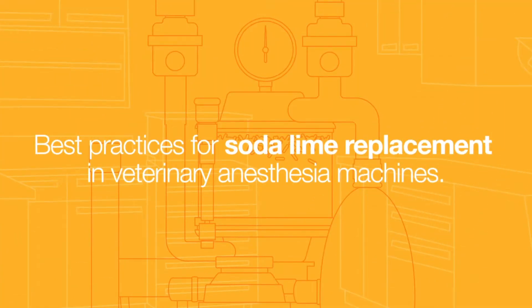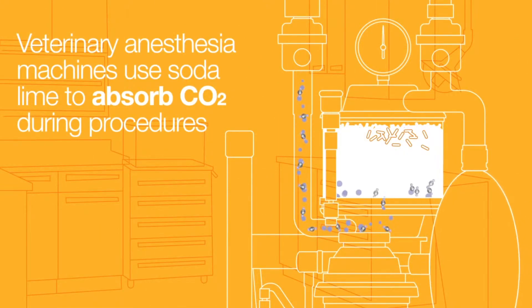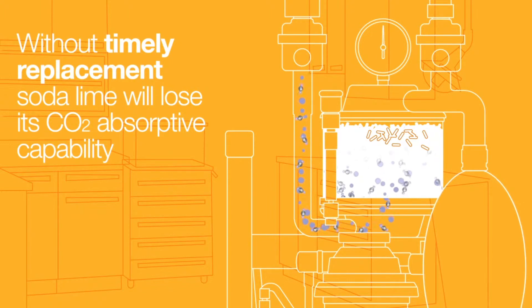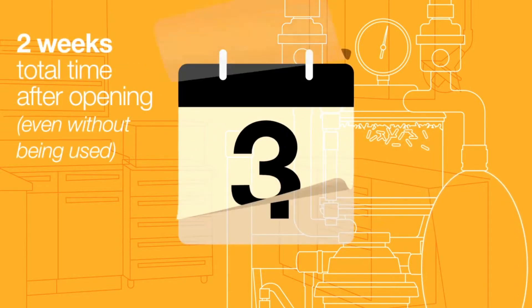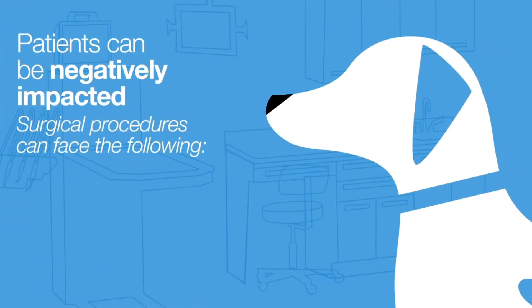Best Practices for soda lime Replacement in Veterinary Anesthesia Machines. Did you know veterinary anesthesia machines use soda lime to absorb dangerous CO2 during surgical procedures? Without timely replacement, the soda lime will lose its ability to absorb CO2. This occurs after 8 hours of average use in surgical procedures, or 2 weeks after opening the package even if the product isn't used in a procedure. Without timely replacement, your patients can be negatively impacted during surgical procedures.